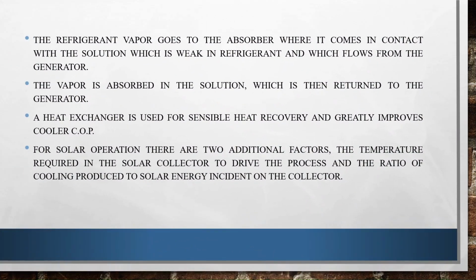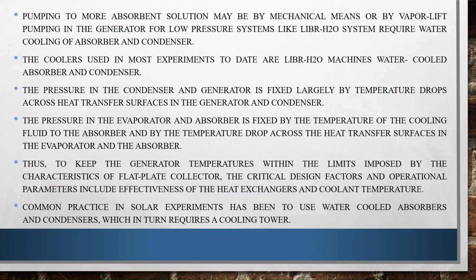The refrigerant vapor goes to the absorber, where it comes in contact with the solution which is weak in refrigerant and which flows from the generator. The vapor is absorbed in the solution, which is then returned to the generator. The heat exchanger is used for sensible heat recovery and greatly improves cooling. For solar operation, there are two additional factors: the temperature required in the solar collector to drive the process, and the ratio of cooling produced to solar energy incident on the collector. That means the higher the intensity of solar radiation, the better the cooling.